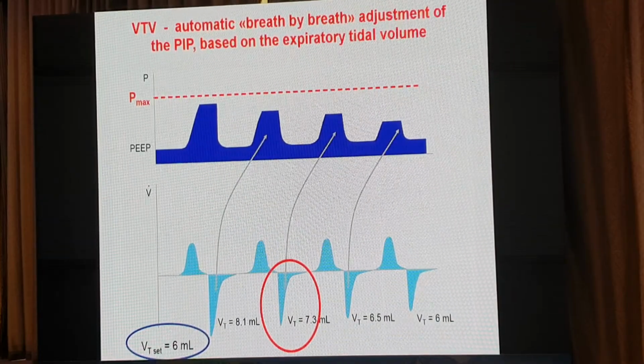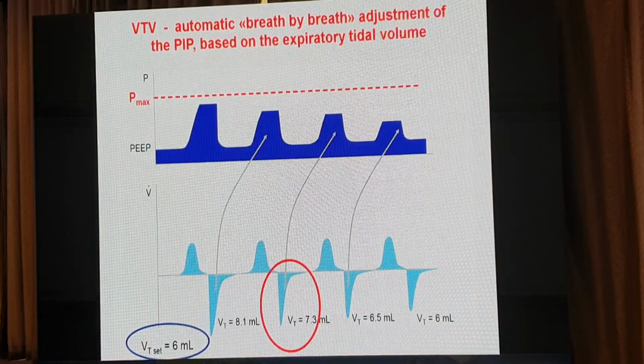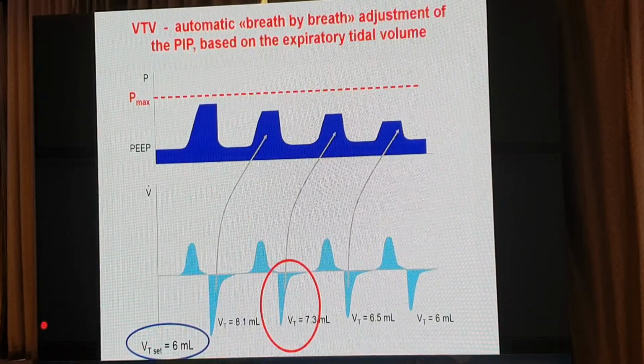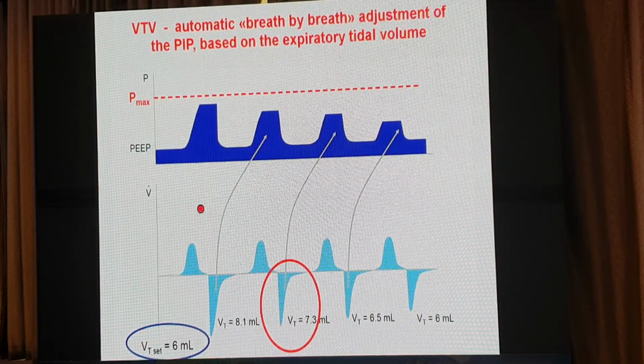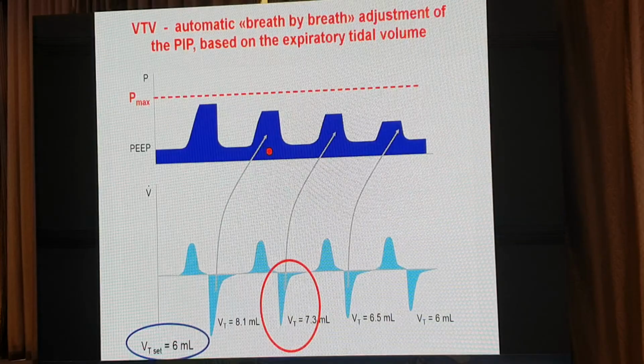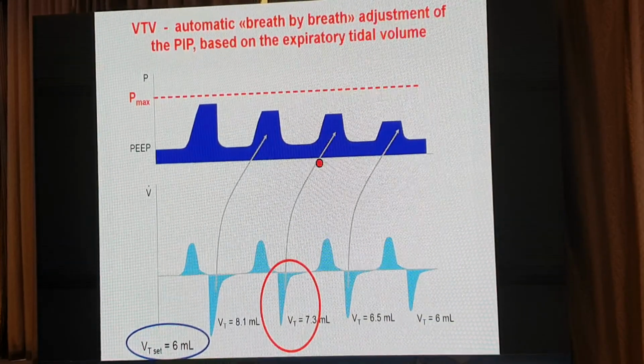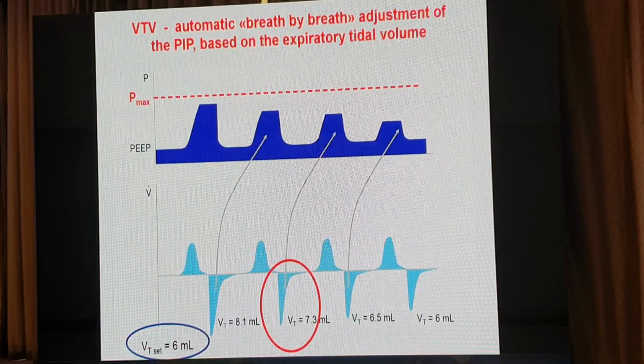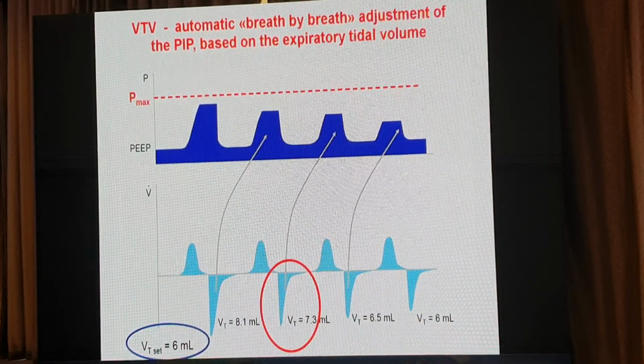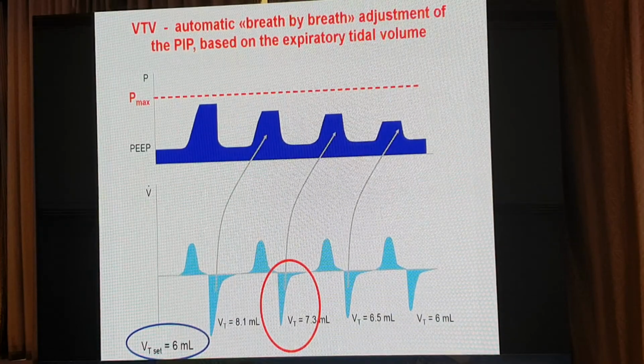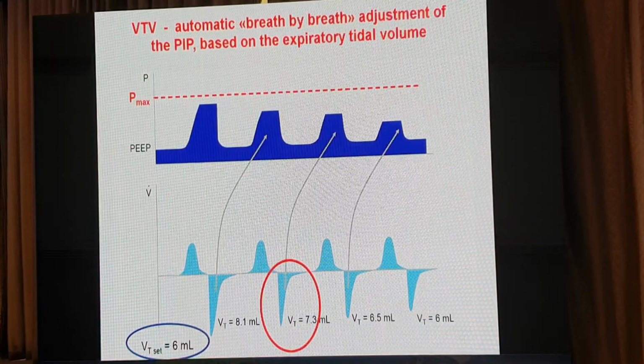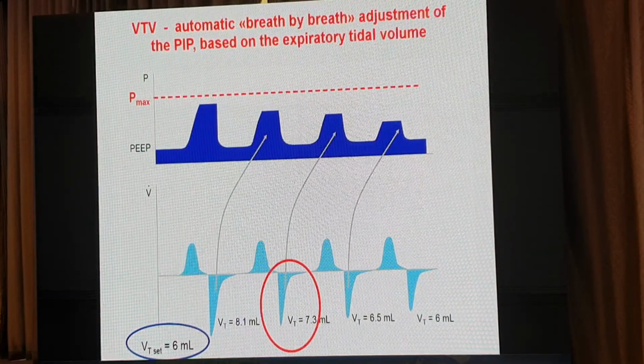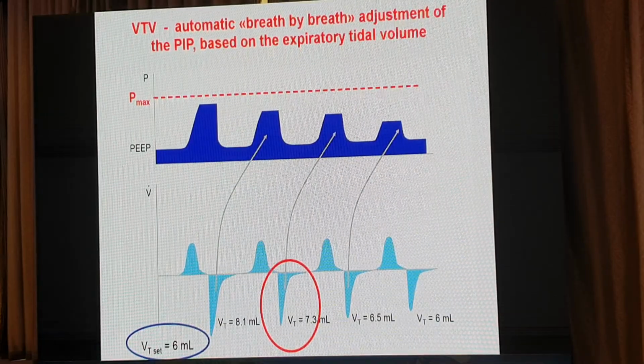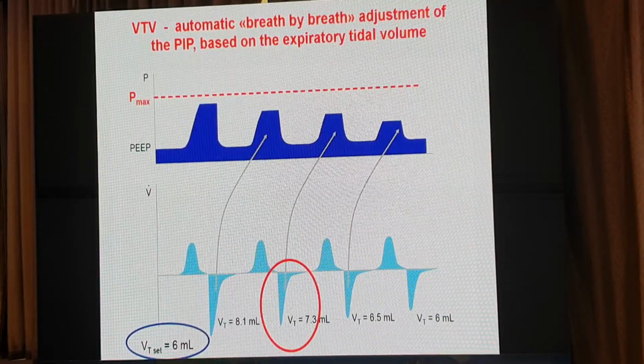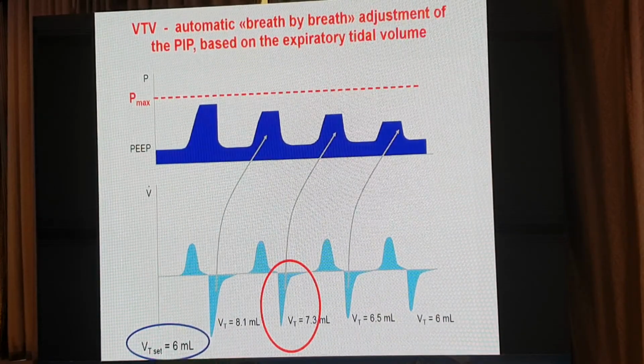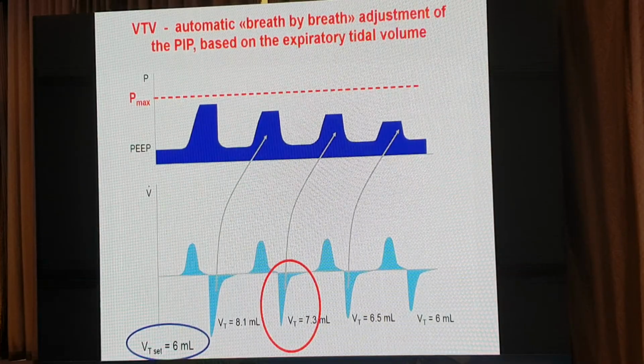In this ventilator, you set the target tidal volume, and then you measure the expiratory tidal volume down here. So you set the volume of 6, and then you measure it, and it was 8, and then you dial down the pressure. Then it goes to 7, you dial down the pressure, and it goes to 6. And then the ventilator automatically adjusts the pressure needed to achieve the set tidal volume from breath to breath. There's no doctor standing there dialing it up and down, up and down. It's adjusted breath by breath. This would be impossible for a human being to adjust in the same manner. So this is just acknowledging that microprocessors are more accurate than human beings in adjusting pressures, I guess.